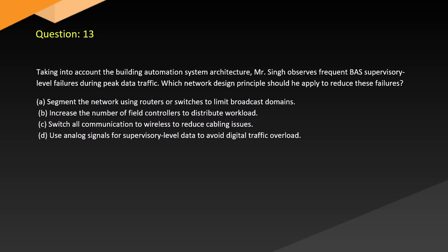Question 13. Taking into account the building automation system architecture, Mr. Singh observes frequent BAS supervisory level failures during peak data traffic. Which network design principle should he apply to reduce these failures? A. Segment the network using routers or switches to limit broadcast domains. B. Increase the number of field controllers to distribute workload. C. Switch all communication to wireless to reduce cabling issues. D. Use analog signals for supervisory level data to avoid digital traffic overload.